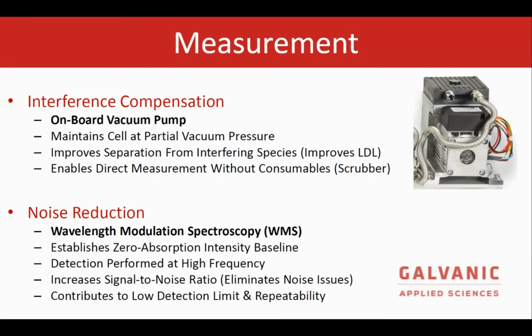Now, how are we doing it? In the design of the AccuLase, we basically use a vacuum pump, as you see in this picture. At the top, we're keeping a partial vacuum pressure in the cell, and that enables us to isolate the line of our interest for the measurement without worrying about the interfering species. So another main advantage of using the vacuum pump is that we do not use any scrubber or any consumables in the AccuLase design.